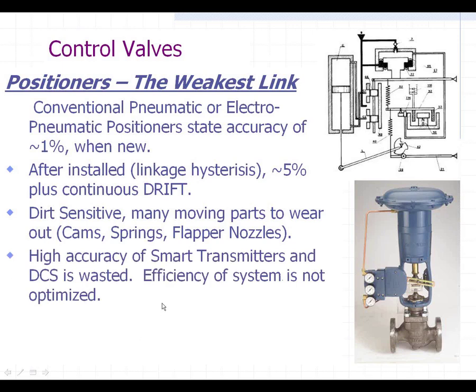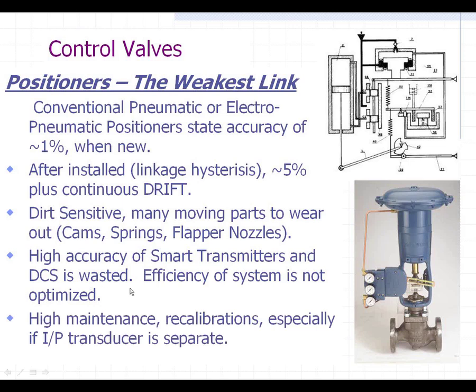So the point is the high accuracy of the smart transmitters and the DCS, in my mind, is wasted. The efficiency of your system just isn't optimized the way it could be. There's a lot of high-maintenance recalibrations required on these, especially if the I/P transducer is separate, which I see in a lot of plants.